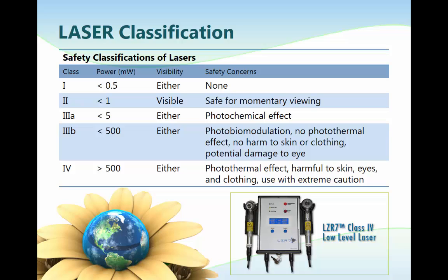Class 3B lasers have a power up to 500 milliwatts. Direct contact of the laser output with the eyes can result in damage, and these lasers must be labeled with 'Danger: visible and/or invisible laser radiation — avoid direct exposure to beam.' The patient, clinician, and anyone in the immediate area must wear goggles during treatment. Class 4 lasers have a power greater than 500 milliwatts. Direct or indirect contact with skin or eyes can be hazardous, toxic airborne contaminants may be produced, and the output can create a fire hazard.